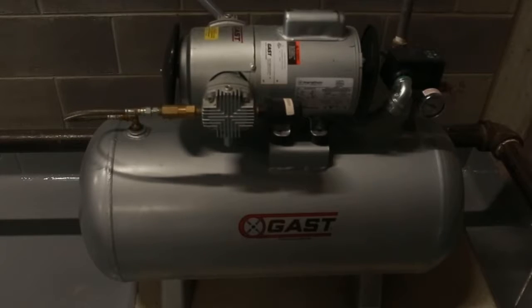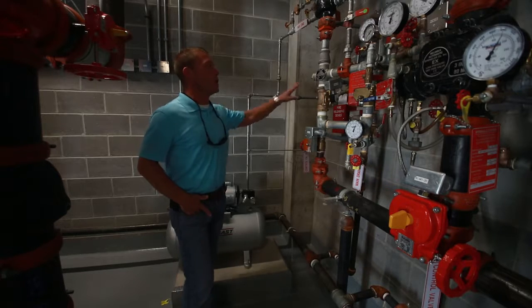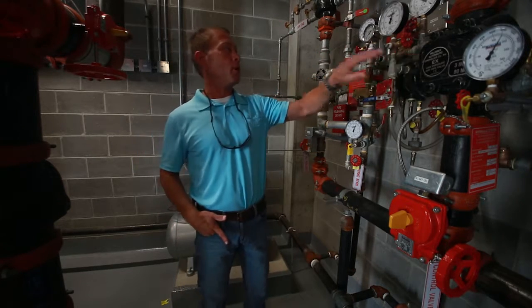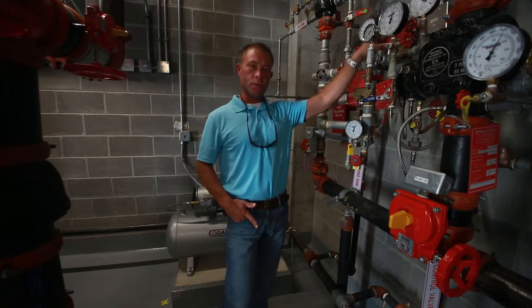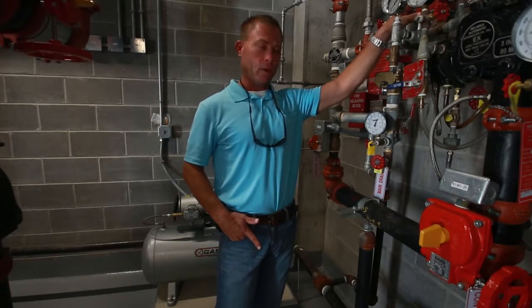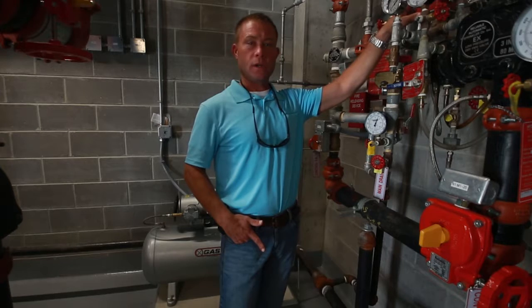The air compressor is a Gast air compressor. It feeds both the pre-action and the dry valve. Both have low air supervisory switches that will send an alarm to the panel if the air gets low.